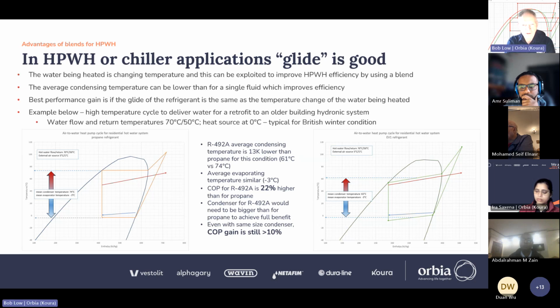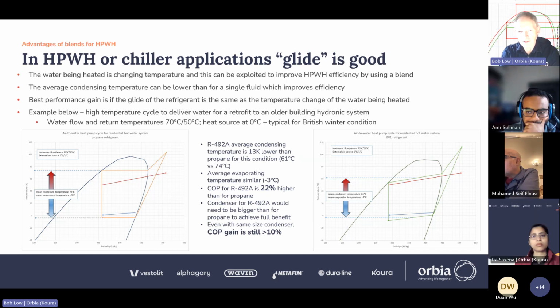The well-known Lorenz cycle here is the appropriate comparison, not the Carnot cycle. So the concept is that we match the temperature change of the fluid, the refrigerant, to the temperature change of the external fluid. If we do that, then the Lorenz theory tells us that the average temperature lift for the cycle is reduced and hence the COP is improved.